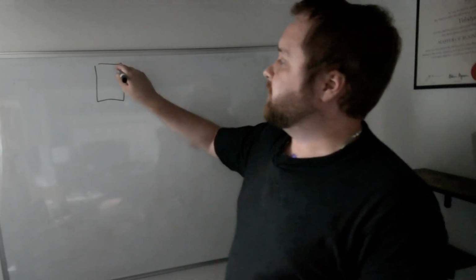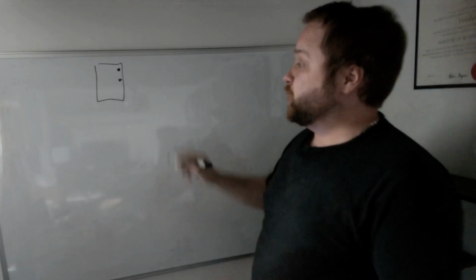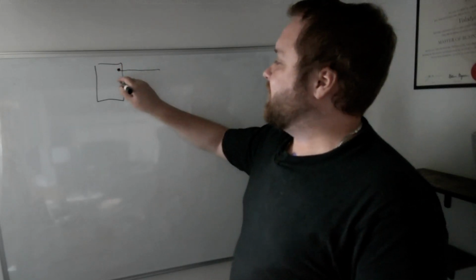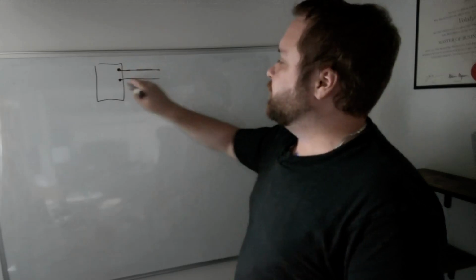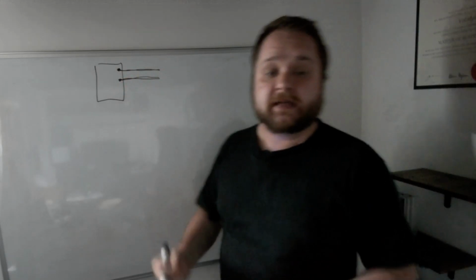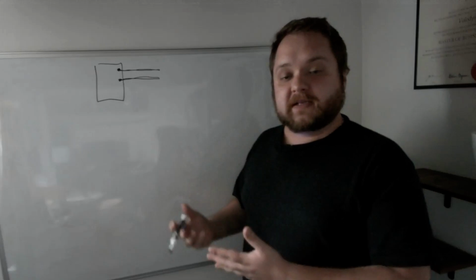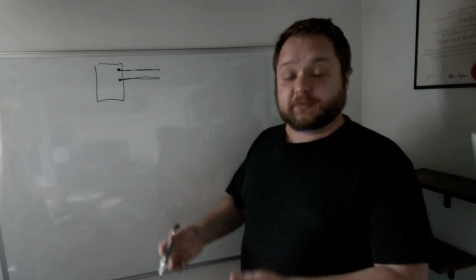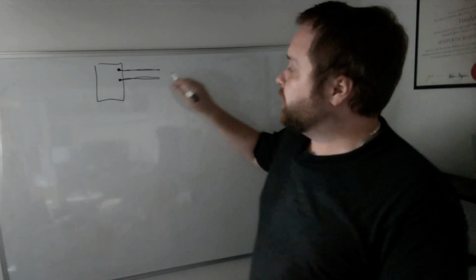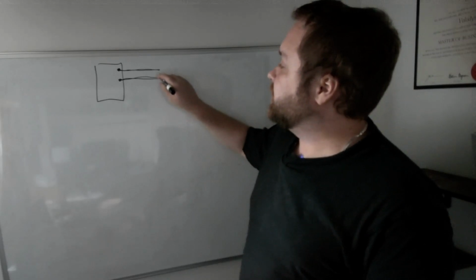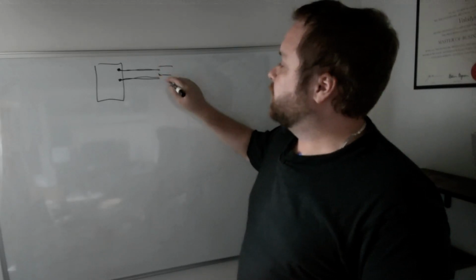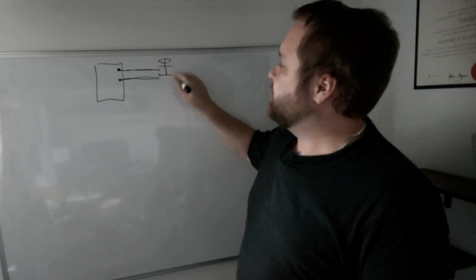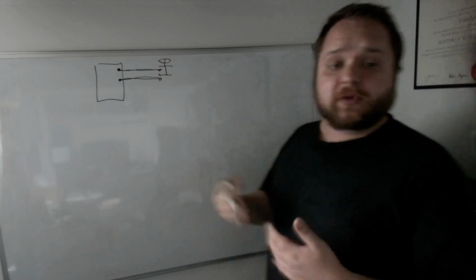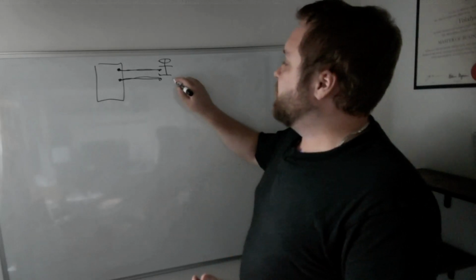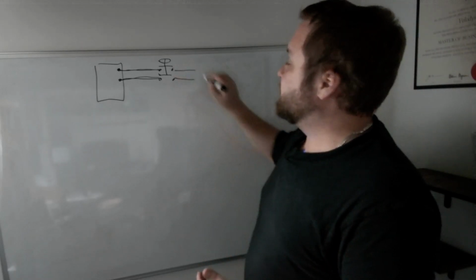So what does that actually mean? The concept is fairly simple, and I want to say analogous to what we discussed with the single channel, but basically instead of having a single wire coming out, every relay is going to have two wires. Now, does that mean that every single device on that chain needs to also have two contacts? And the answer is yes. So in order for it to be considered safe, you also now have what's called dual channel safety. And so every push button and every e-stop or light curtain or any safety device is basically going to have two sets of contacts instead of one.